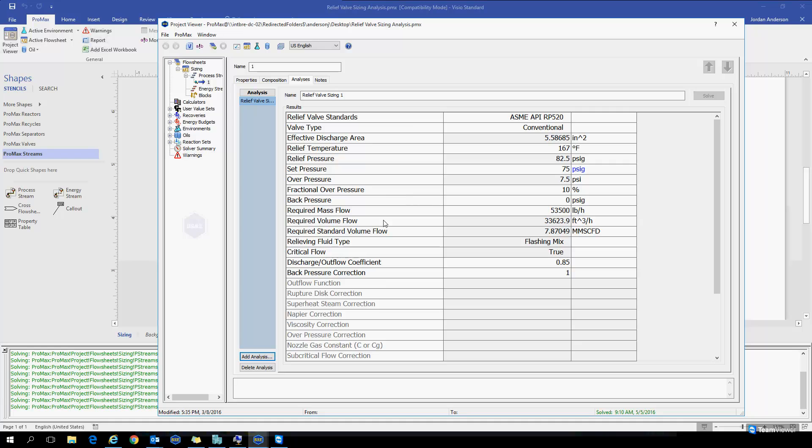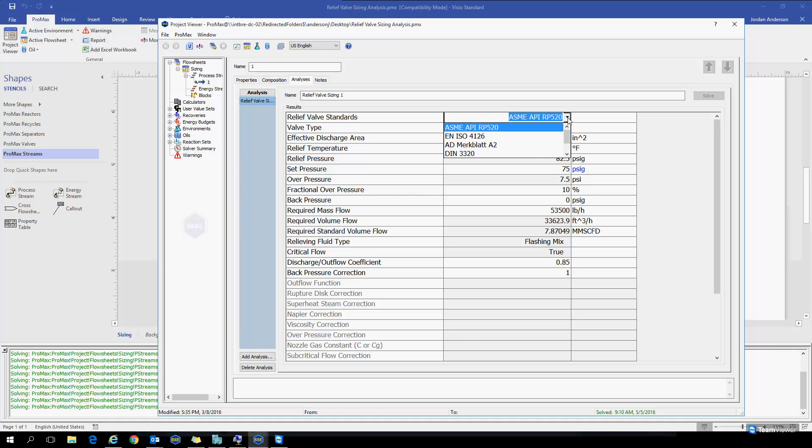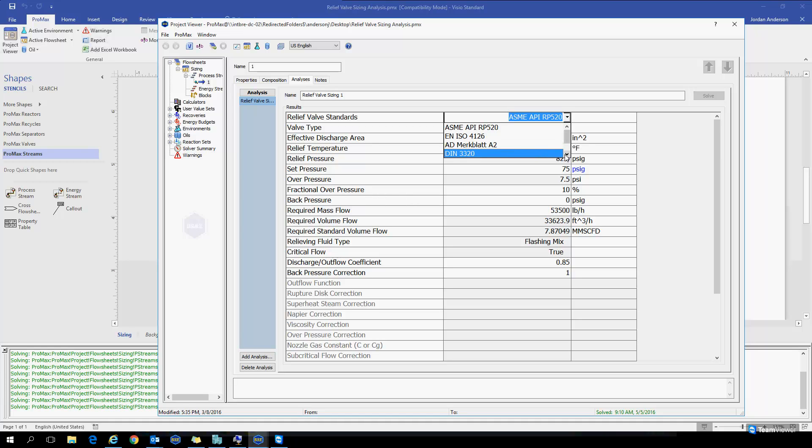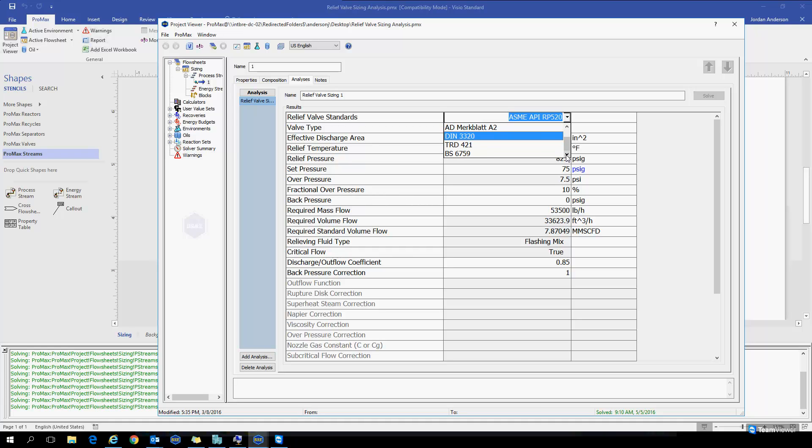Let's talk about the different properties we have here. The very first thing that we would choose is which standard we'd like to use. You'll see that the ASME API RP520 is the default and it's the most commonly used. But we do have other standards that are listed here in the list, and these would be used depending on your situation or your location in the world.